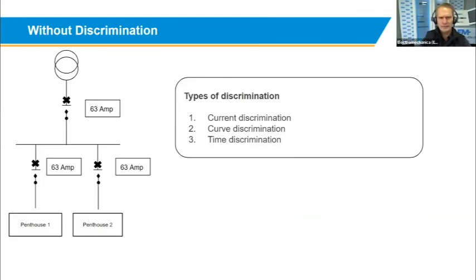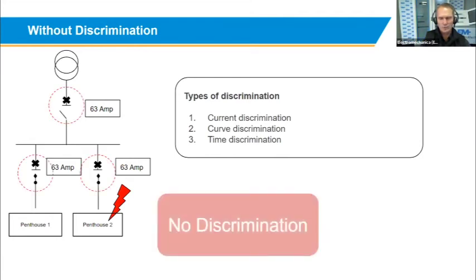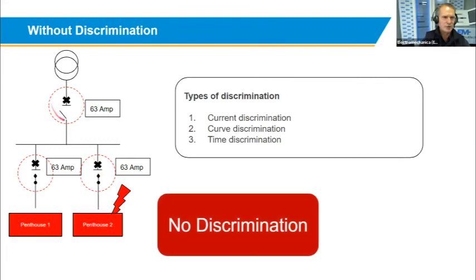Then what's going to happen without discrimination? In the previous application, you saw there was a 125 amp breaker upstream and 63 amp at the 2 penthouses. In this application, the person doing the installation did not look at what they were doing, and they installed a 63 amp circuit breaker as a main incomer, and then a 63 amp at each penthouse. So penthouse 1 is pulling 40 amps, and penthouse 2 goes into an overcurrent scenario. Again, the bimetal starts heating up, and before the breaker can open, you lose your upstream circuit breaker, and both penthouses go off.